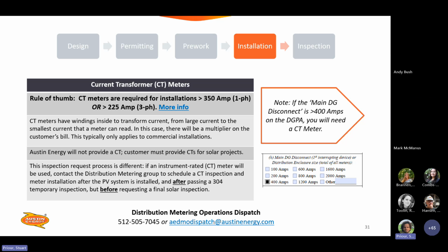Between 400 and 600 is a trans socket, right? So that's the big one that's got the CTs integrated into the enclosure itself. Above 600, so 601 and up, you'll have a meter enclosure and then a CT enclosure that are separate from each other. So what are CTs?